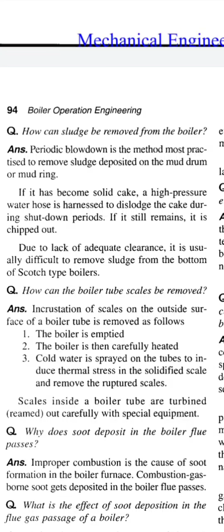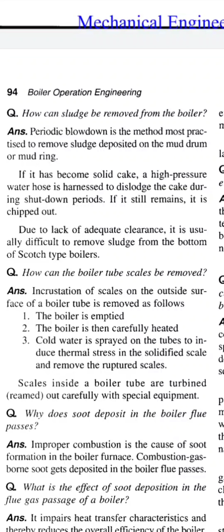Question: how can sludge be removed from a boiler? Periodic blowdown is the method most practiced to remove sludge deposition on the mud drum or mud ring. If it has become a solid cake, a high pressure water hose is used to dislodge the cake during shutdown periods. If it still remains, it is chipped out. Due to lack of adequate clearance, it is usually difficult to remove sludge from the bottom of Scotch type boilers.